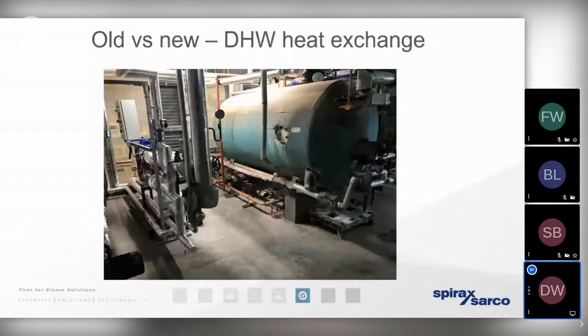So that oversizing means that it can be far more susceptible to scaling. If we're distributing steam at a high pressure, that high condensing pressure and temperature means that we're more susceptible to water chemistry creating scaling on the tube bundle assembly itself. That scaling is going to require stripping down and inspection periodically. And that's on top of the pressure equipment directive and the Legionella inspection costs. So we're going to need a significant amount of downtime and manual handling. So we keep mentioning the benefits of efficiency by being able to generate hot water from steam instantaneously. But it's always worth bearing in mind the maintenance, the downtime, the inspection costs, the risks, and the health and safety benefits that a move away from a storage solution to an instantaneous solution can bring.